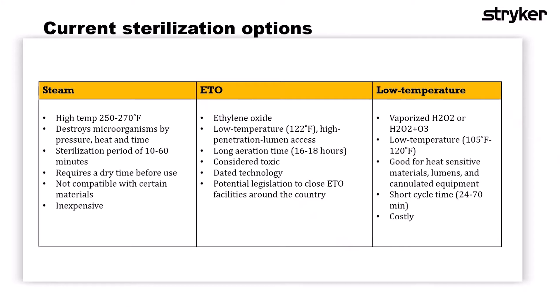Steam is not compatible with certain materials. One of the big drivers for low temperature sterilization is those items that are heat sensitive and could be damaged during steam sterilization. Steam sterilization is also the most inexpensive form of sterilization that we have on the market.